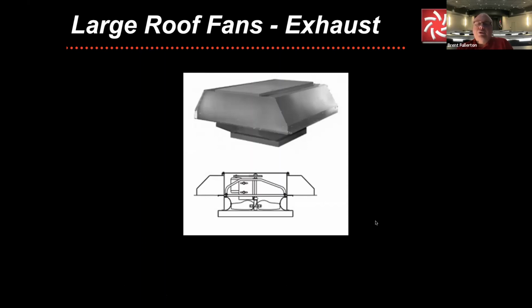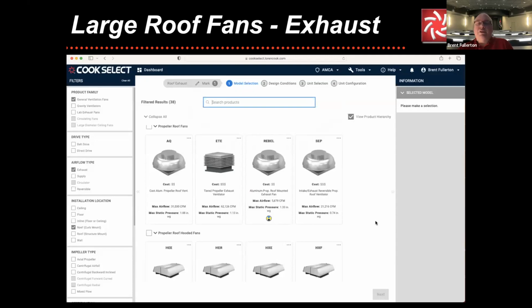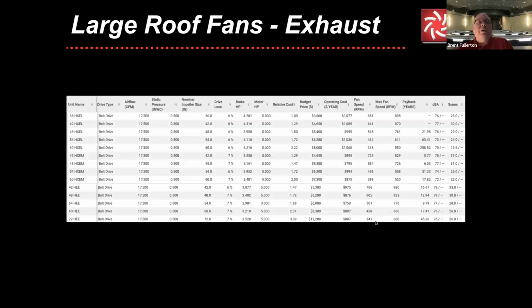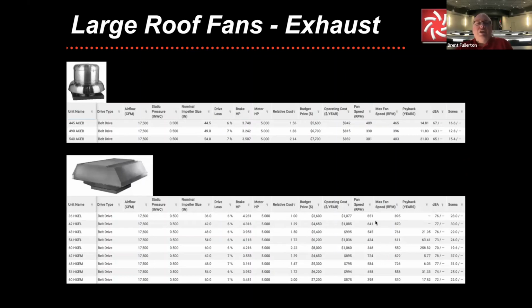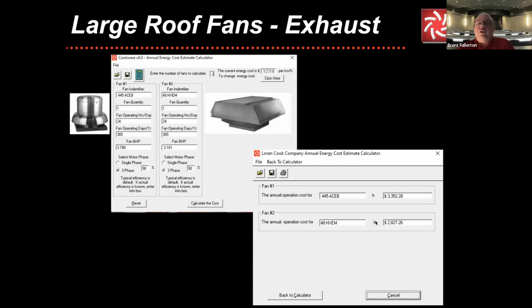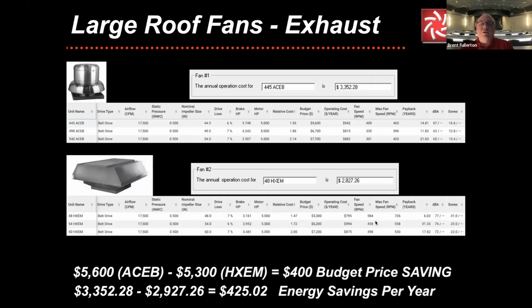But this particular product, in certain parts of the country, certain design build firms, certain consultants, this becomes their number one go-to style of product. And we'll dive in and look at some of these different prop styles of products. Now, here's the grid, but let's dive in and look at it a little closer. So where we had the large scale power roof ventilator versus the prop, you'll notice that you dropped your brake horsepower significantly and quite a bit of energy savings. So in this case, you have a first cost savings of your purchased product of $400, but you also have an annual energy savings of over $400 per year.